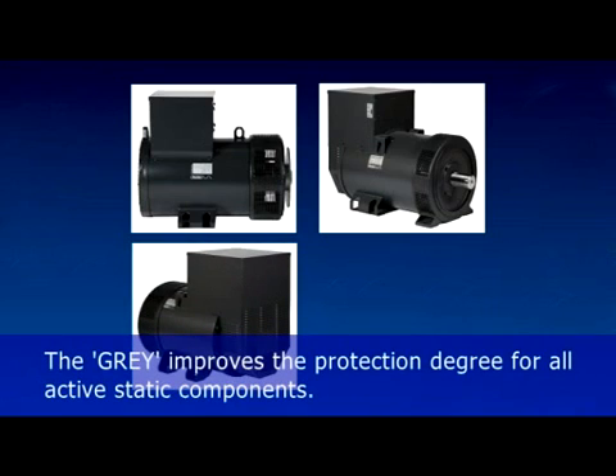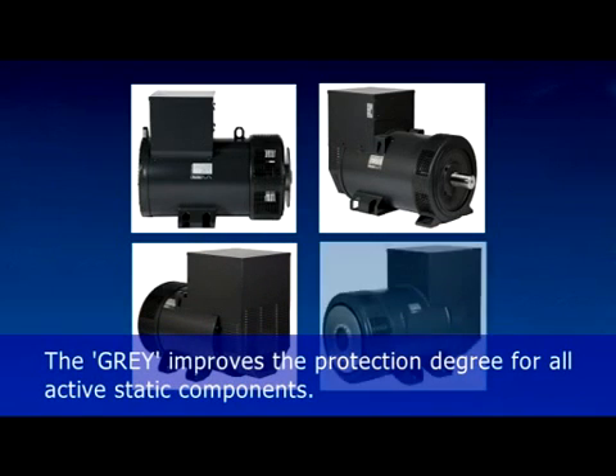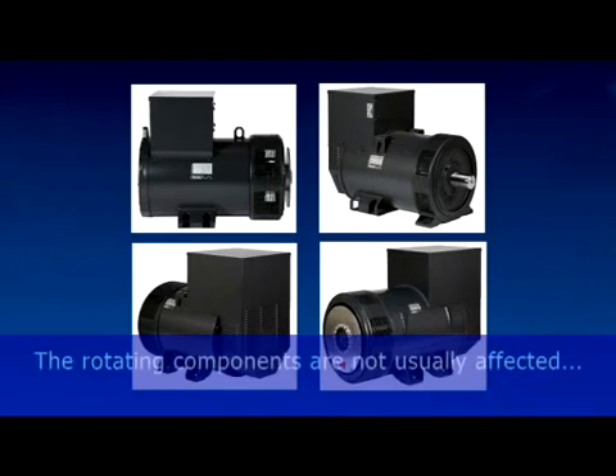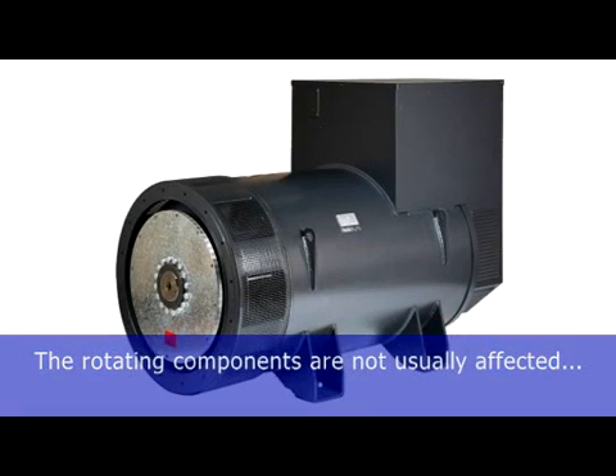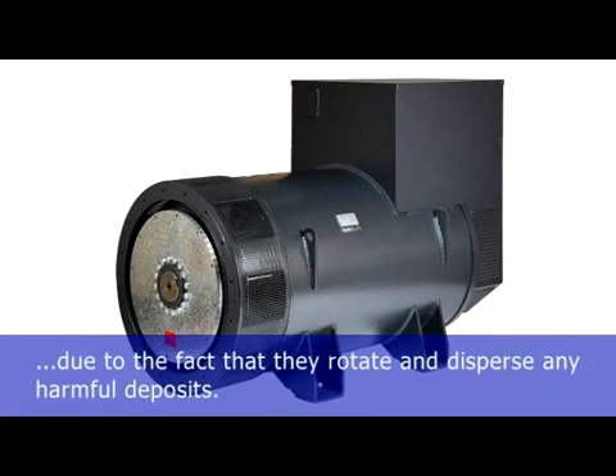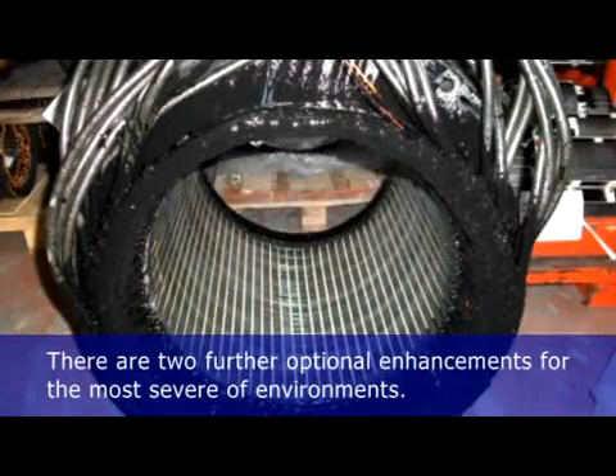The grey improves the protection degree for all active static components. The rotating components are not usually affected due to the fact that they rotate and disperse any harmful deposits. There are two further optional enhancements for the most severe of environments.